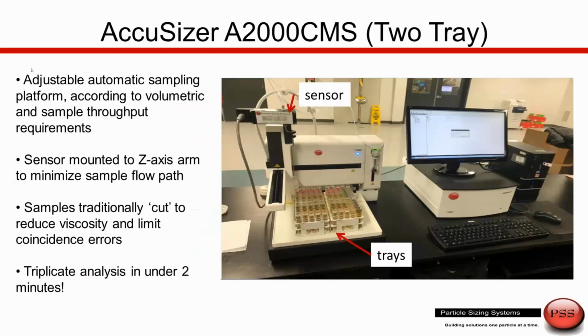Here is an image of the AccuSizer A2000CMS. This system has been set up with two trays. We could have a single or dual tray system set up on what is essentially an auto sampler. On this auto sampler, you'll see the sensor up here. This is where the measurement is made. Over here, you'll see a syringe, and this syringe is going to do two functions. It's going to aspirate the sample up through the sensor, and then after the measurement, it will push it out to waste. So we have the sensor, we have the tray, this is the counter, which is the pulse height analyzer, and the computer and monitor running the system. What's going to happen is there's a needle coming down from here, and it is going to come over and sample each of these tubes, take the measurement, push the sample to waste, and in between each measurement, it's going to clean the needle to make sure there is no cross-contamination.